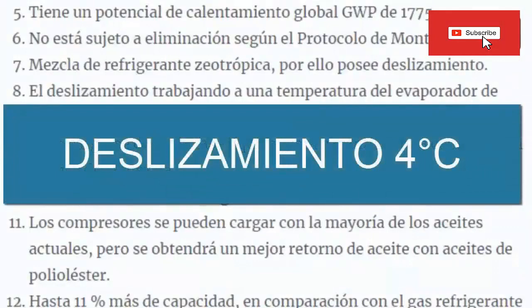6. Not subject to deletion under the Montreal Protocol. 7. It is a zeotropic refrigerant mixture, therefore it has slippage. 8. The slip working at an evaporator temperature of minus 18 degrees Celsius is approximately 4 degrees Celsius.